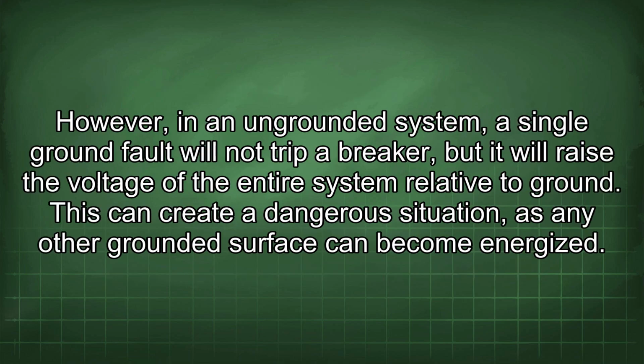However, in an ungrounded system, a single ground fault will not trip a breaker, but it will raise the voltage of the entire system relative to ground. This can create a dangerous situation, as any other grounded surface can become energized.